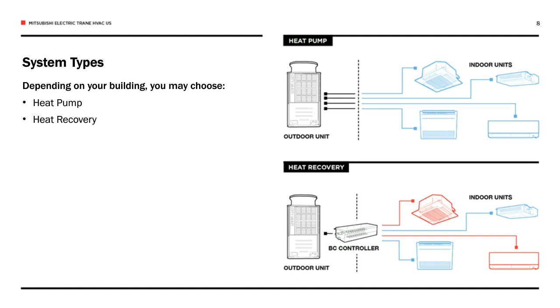VRF systems can also be applied in two configurations: air source and water source. Air source systems use air as the heat transfer medium, expelling rejected heat into the air outside of a building. Water source systems use water as the heat transfer medium, expelling rejected heat from the space into a water source typically located inside the building.